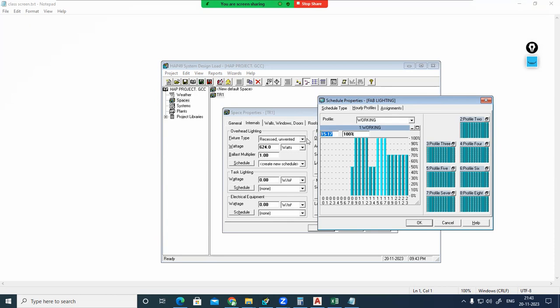Even after the office, people might be there. So 18 to, let's say, 2-hour allowance, 18 to 20, you can consider that is 50%. So light fittings might be using. Then from 21 to 23, no one will be using the light fitting, that will be 0. So this is my profile of working day. Light fitting will be using in this profile. So with respect to this profile, only the software will be calculating the simulation, selection of light fitting load. Okay, it's my working.